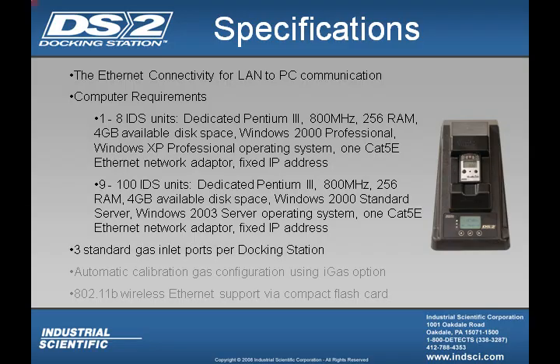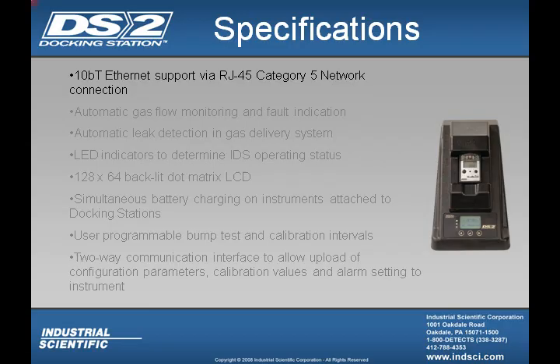And on the back of your docking station, you have 3 standard gas inlet ports. And you also have automatic calibration gas configuration using the iGas option. And for special applications, wireless connectivity is available using 802.11b wireless Ethernet support via compact flash card. And for wired connections, we would use a 10BT Ethernet support via RJ45 Category 5 network connection. Automatic gas flow monitoring and fault indications is also available in your DS2, as well as automatic leak detection in the gas delivery system.